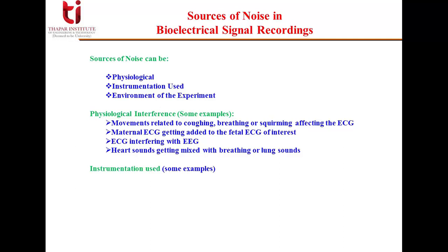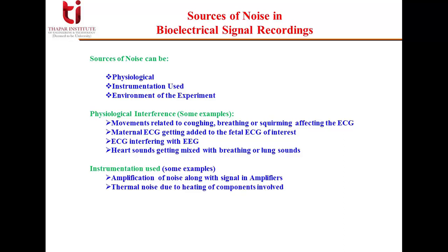Due to the weak levels of most biomedical signals at their source, high amplification factors are required. So electronic noise in the instrumentation amplifier also gets amplified along with the desired signal. There can also be thermal noise due to heating of instruments or components. So they contribute to the instrumentation noise.